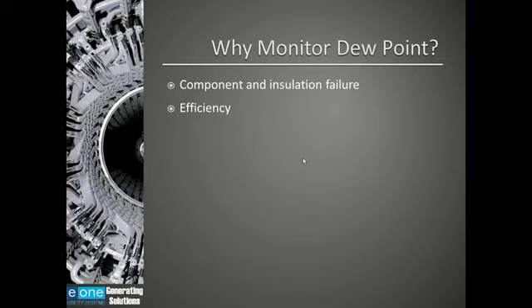Now I'm going to talk a little bit about monitoring dew point. Why do we monitor dew point? In my opinion, and this author's opinion, the most important reason is component and insulation failure. You want to keep your dew point low so that you do not create situations in the generator where components will fail. A secondary reason is efficiency. However, I will state that it takes a large amount of moisture in a generator to affect the efficiency of the generator. Some other points about dew point.